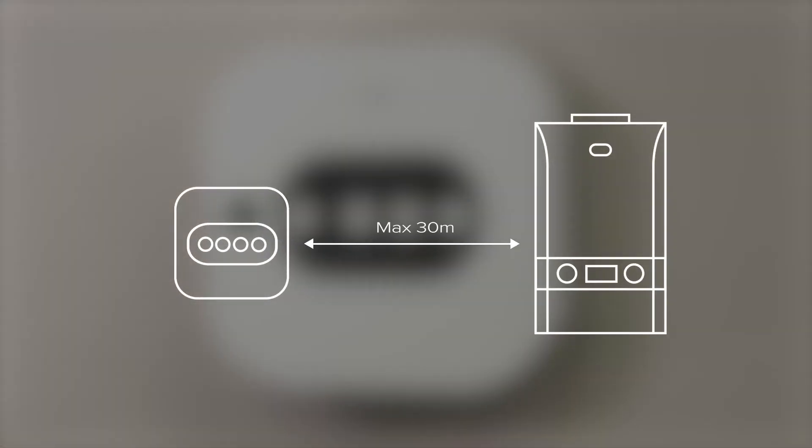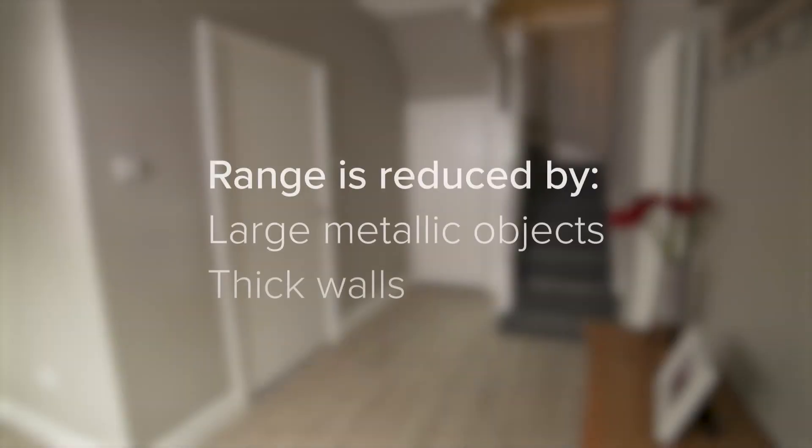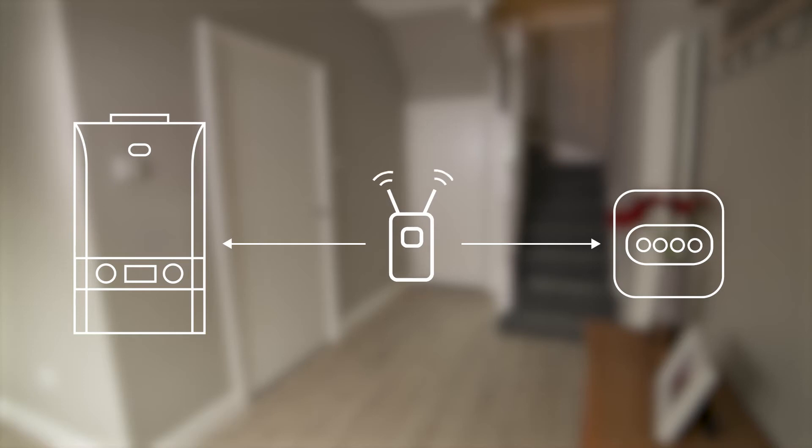The maximum range for this communication is up to 30 meters. Range is reduced by large metallic objects and thick walls. If the distance between the smart interface and smart wiring center is troublesome, you may wish to consider adding a Zigbee booster to the system to increase the range.